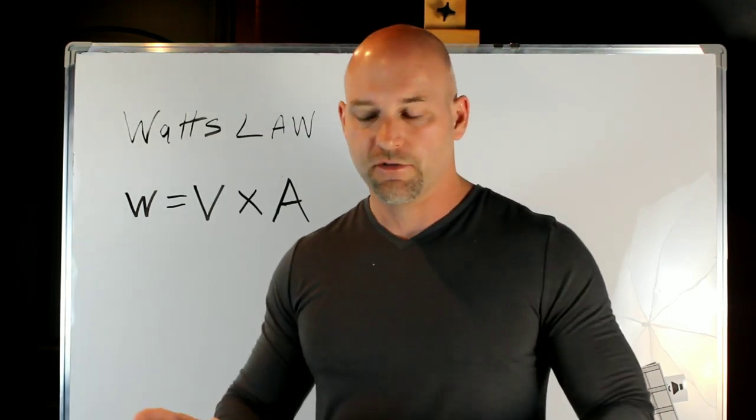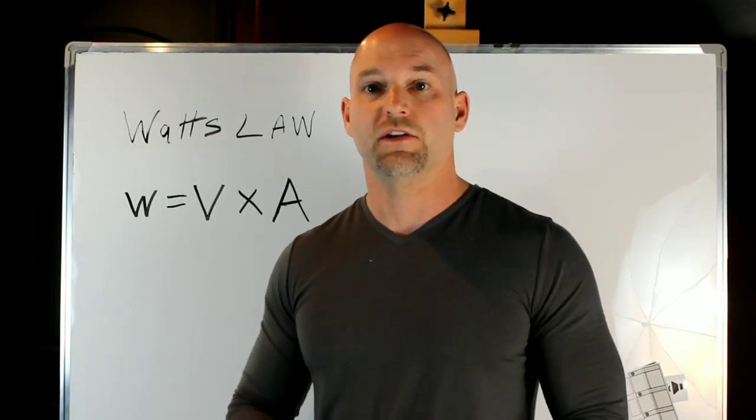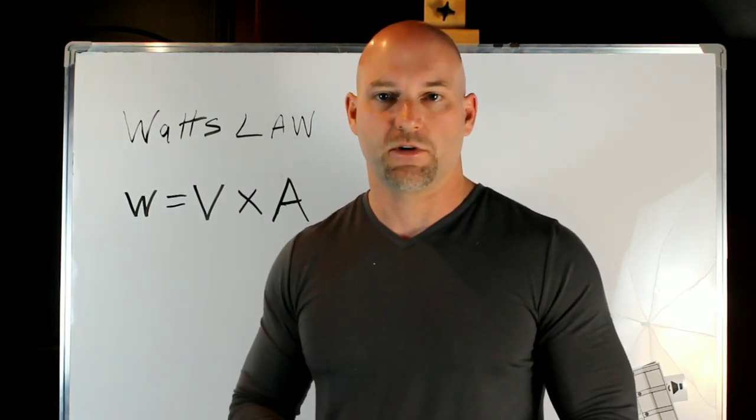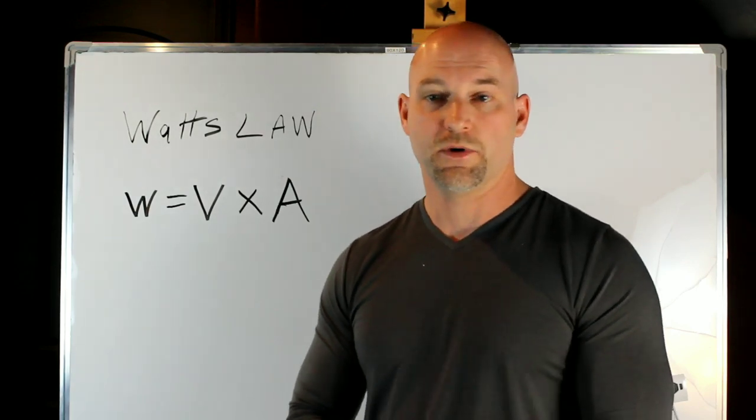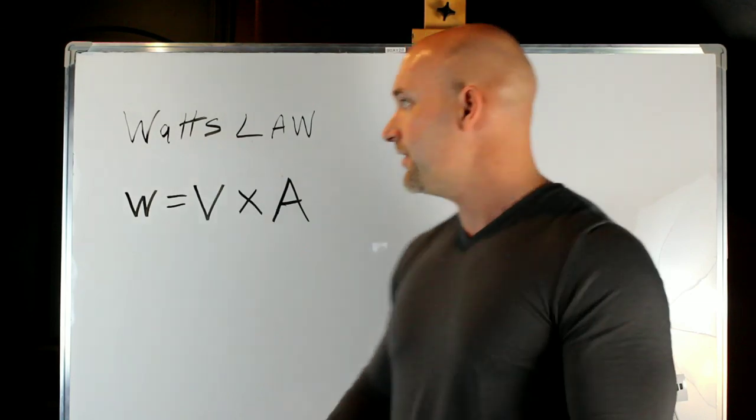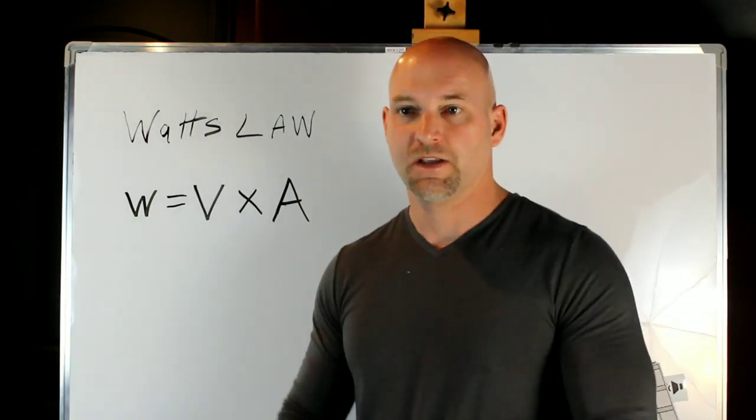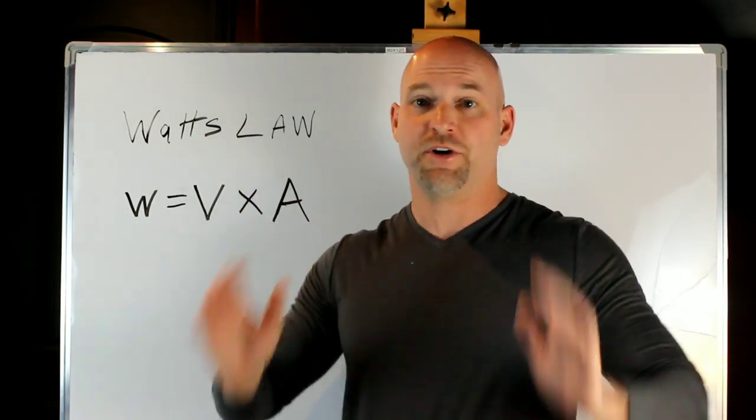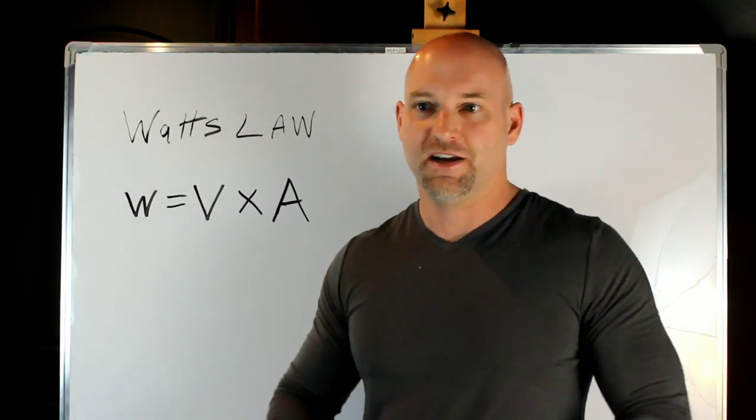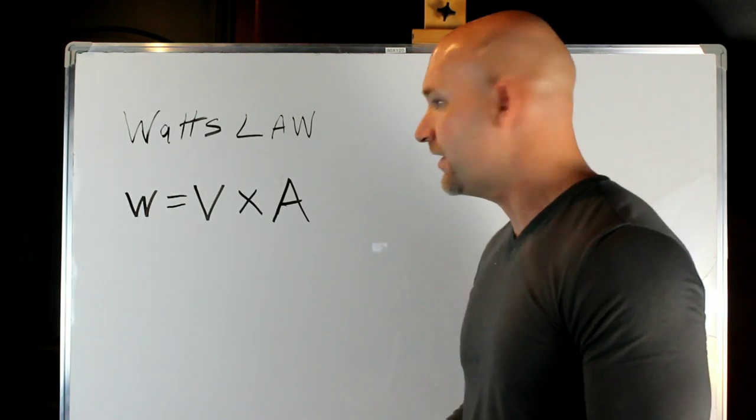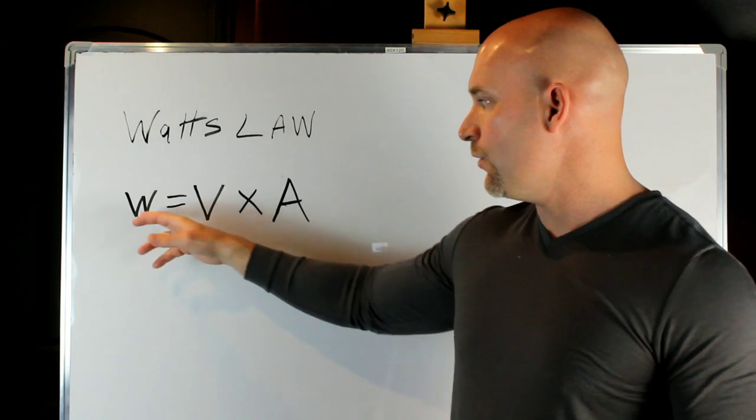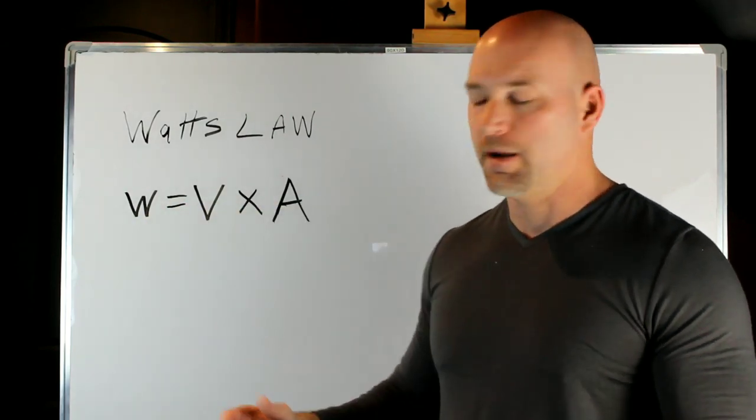If you wanted a 20 amp circuit and you've got a 15 amp breaker in there, you would have to confirm the wire in the wall is rated for that breaker and that breaker is going to protect it properly. You don't want to burn your house down. So now that we've got that covered, let's look at how we can calculate how much of a load we're going to apply to a circuit. To do that, we're going to use something called Watts law. Everyone's heard of Ohm's law. This is Watts law.